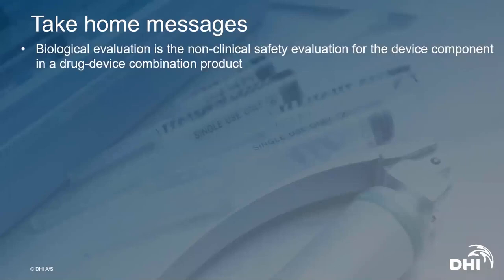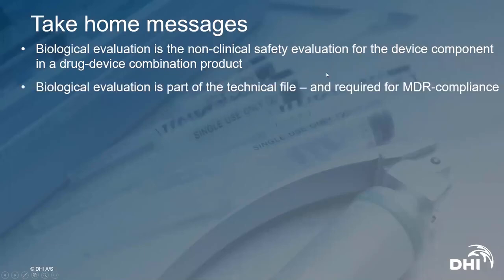So the take-home messages from this webinar is that for doing a biological evaluation, that's the non-clinical safety package for the device component of your drug-device combination product. It's part of the technical file for the medical device component of your device, and it's required for MDR compliance, and you will also need to submit that to your notified body and have sort of that certificate when you submit your file for your combination product to authorities.